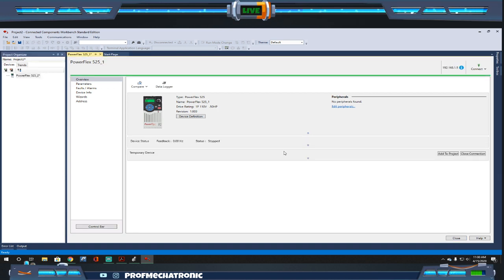Typically I've used that on stations with 10, 15, 20, or 30 VFDs where I want to get the parameters set up ahead of time. If you're doing 1, 2, maybe 3 or 4, even up to 5, you could easily set your parameters using the commissioning tool on site as you go—you don't really have to do that pre-engineering. But depending on your time frames and project rollout, sometimes it's easier to have those parameters and setups done ahead of time.